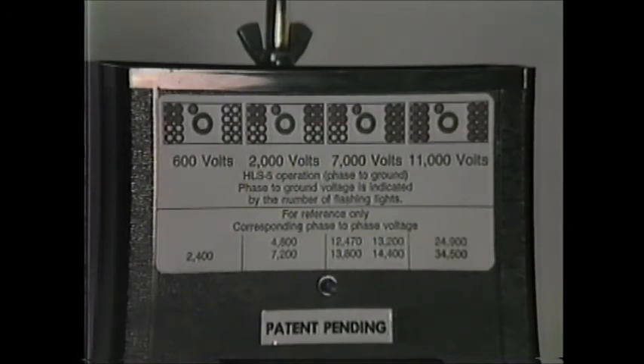Adapters are available to allow the HLS 5 to be used on 15 through 35 KV underground systems. These adapters allow the HLS 5 to be placed directly on the underground bushings.